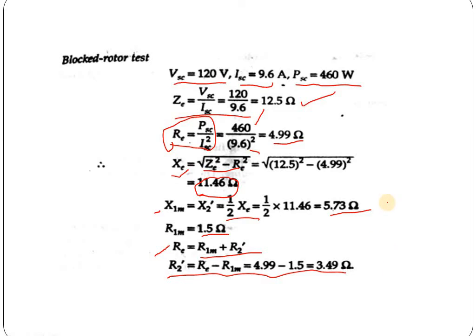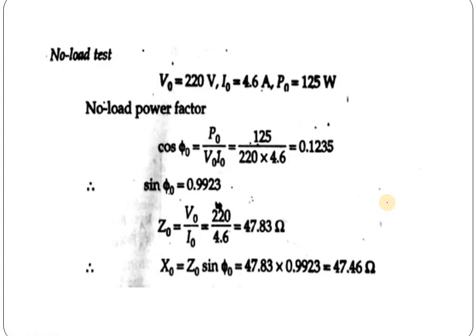So from the block rotor test, we have calculated the equivalent resistance, equivalent reactance, main winding reactance, and the value of R2 dash, which is the rotor referred resistance. Next, we will calculate the no-load test data. V0, the no-load voltage from the voltmeter reading, is 220V. I0, the no-load current from the ammeter reading, is 4.6A. The wattmeter reading at no-load condition is 125W.